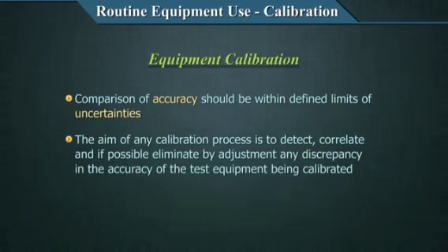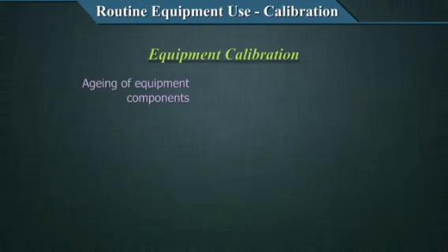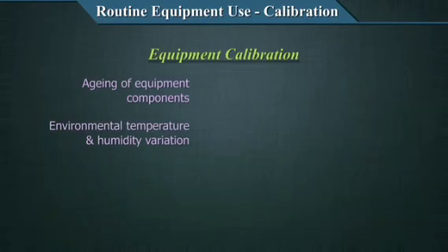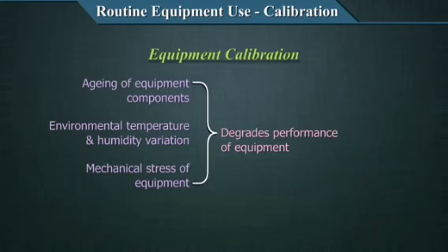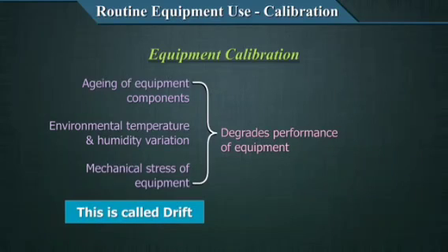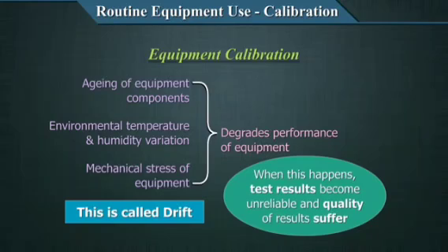Thus, the aim of any calibration process is to detect, correlate, and if possible, eliminate by adjustment any discrepancy in the accuracy of the test equipment being calibrated. I hope that is clear. As components age and equipment undergoes changes due to variation in the environmental temperature and humidity or sustains mechanical stress, the performance gradually degrades. This is called a drift. When this happens, test results become unreliable and the quality of the results suffer.